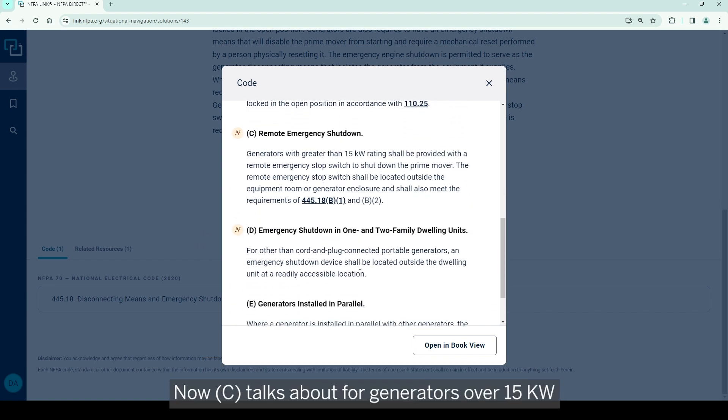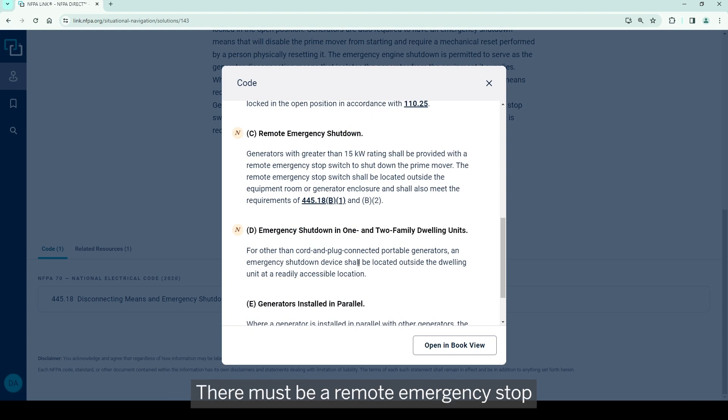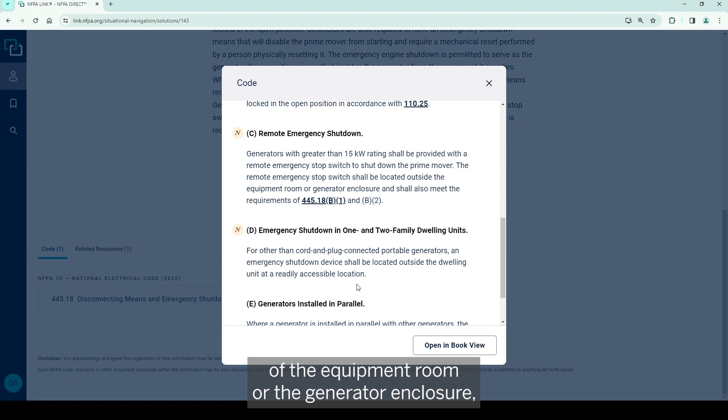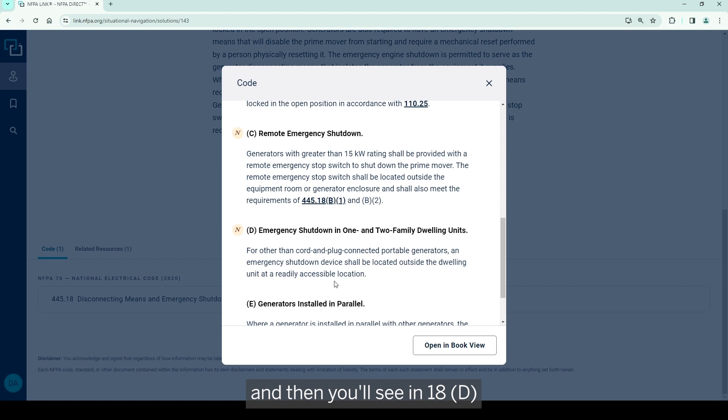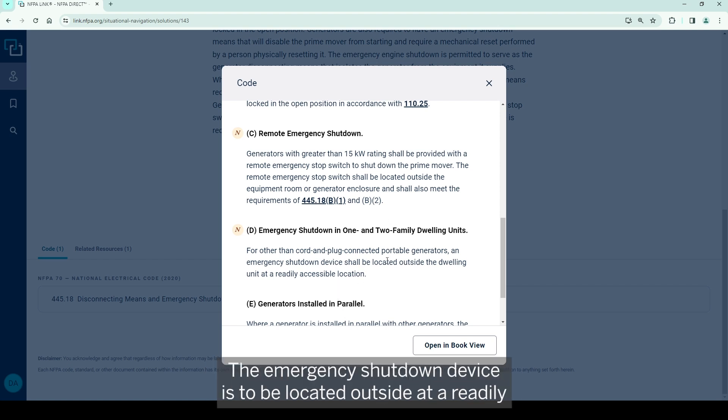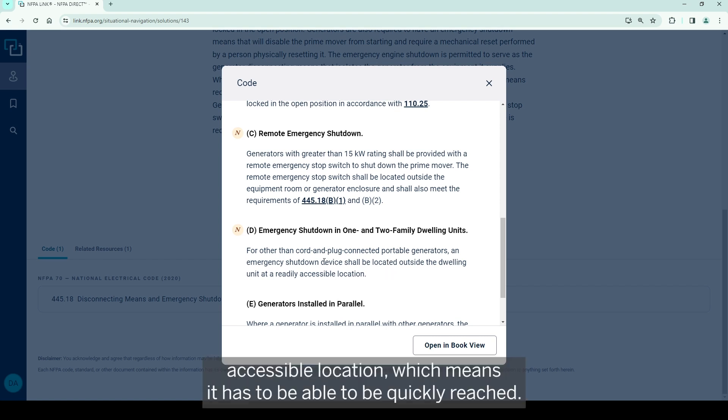Now C talks about for generators over 15 kW there must be a remote emergency stop switch to stop the prime mover, located outside of the equipment room or the generator enclosure. And then you'll see in 18D, for permanently mounted generators at one and two family dwelling units, the emergency shutdown device is to be located outside at a readily accessible location, which means it has to be able to be quickly reached.